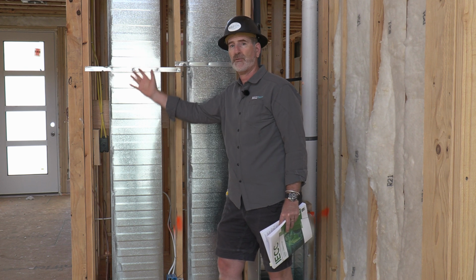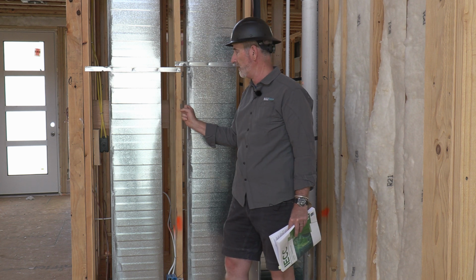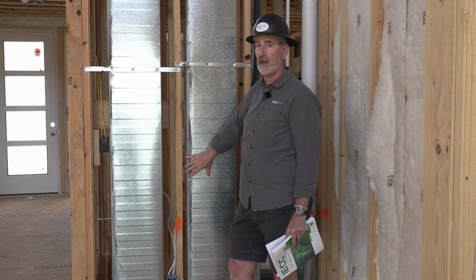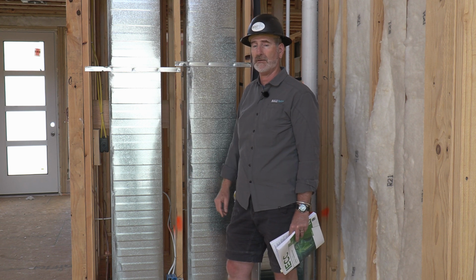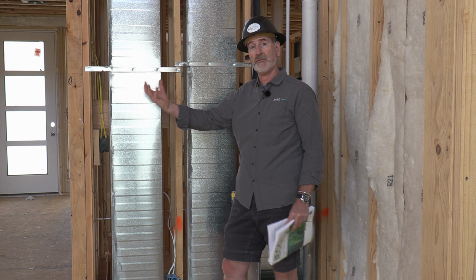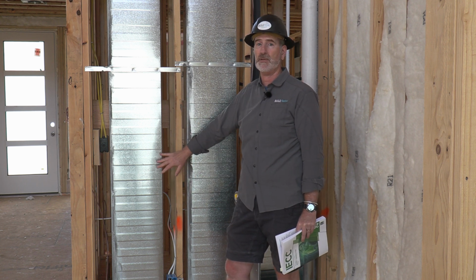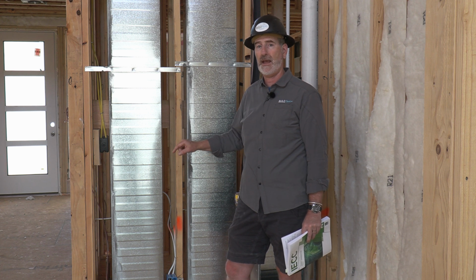If they had put drywall up and were trying to take pressurized air back to the furnace through the cavity that was created with drywall and wood studs, that would not be compliant with the code here. So they've done a good job here, but we wanted to just point that out, that you cannot use building cavities as pressurized ducts. In this case, it would be a negative pressure pulling air back to the furnace, but you can't do it on the supply side, on the positive pressure, as well. And it turns out that most often when you see building cavities used as duct systems, it's on the return side.